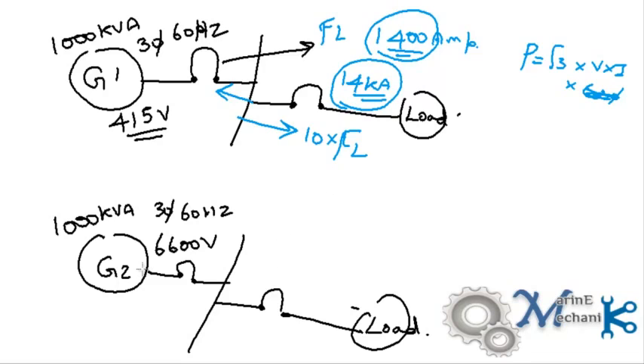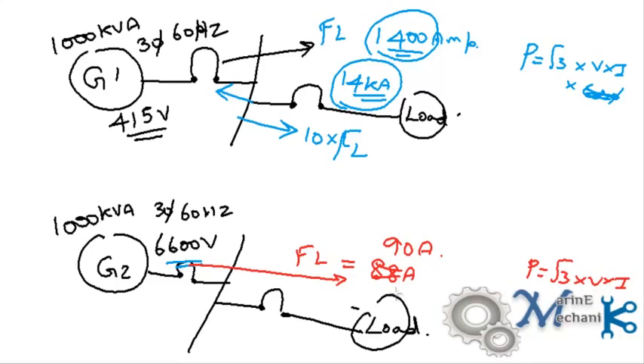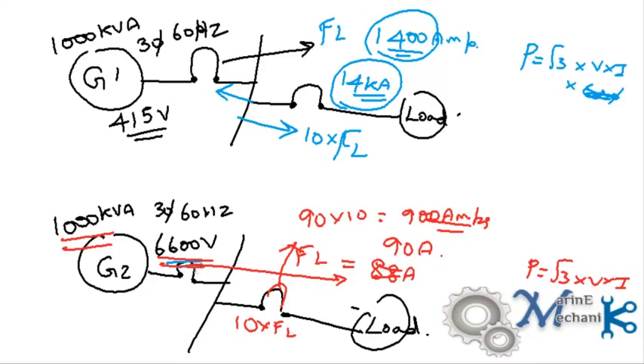Now with a similar structure and calculation, we're going to calculate for 6600 volts. Similarly, calculate with the help of the formula √3 V into I. You'll get the full load current for the generator operating at 6600 volts to be just 88 amps, roughly, let's say 90 amps. As a thumb rule, again we design for just 10 times the full load current. So I have to design my circuit breakers for just 90 into 10, that is 900 amps. That's it, which is going to reduce the size of the circuit breakers and protection devices and help to save a lot of cost, a lot of money. So that's the main advantage we get by increasing the voltage. It is for this reason we operate at high voltage on board certain ships.